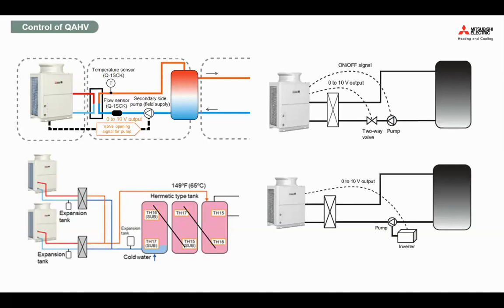So here are some of the basic information on control for the QAHV. The unit will be able to send a 0 to 10 volt signal to open the two-way valve to different positions, and send an on and off signal to tie into the pump, or you can send a 0 to 10 volt signal directly to an inverter-driven pump to control the flow depending on what's required. Here, the top two and the one on the right-hand corner are the configuration for a single unit.